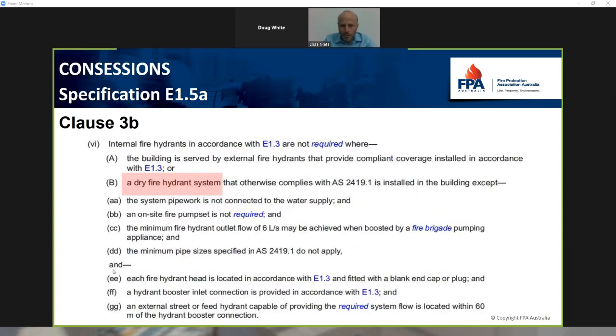Another large concession was the dry hydrant. Dry fire hydrant systems are essentially a stock standard AS2419 system, except that it's not connected to a water supply. It still has a booster inlet, and relies on the fire brigade to get water from the street, plug into the booster and charge that dry hydrant system full of water. Obviously, that means we can get away without installing all of the tapping and the backflow prevention and the whole water supply, potentially pumps and tanks and everything for a hydrant system. We no longer need those. And also the routine service, which, as I told you, is 5 times more than the cost of installing it, all of that disappears as well. So that dry hydrant concession is significant.